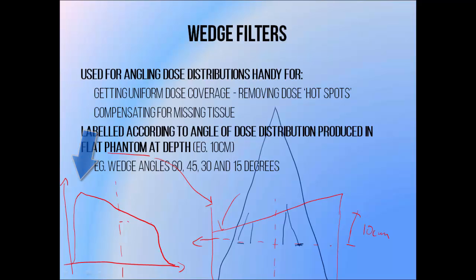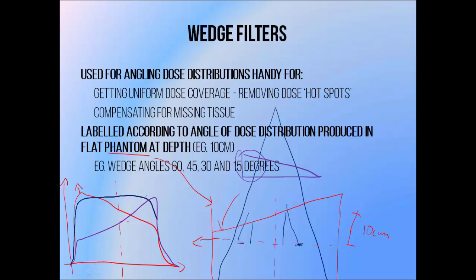But if we put a wedge filter in the way, it will attenuate the beam more on the shallower side and reduce the dose. This can be used to balance out the effects of the angled surface and produce a flat dose distribution. Textbooks will often call this compensating for missing tissue — they just mean the part that stops the surface from being flat.